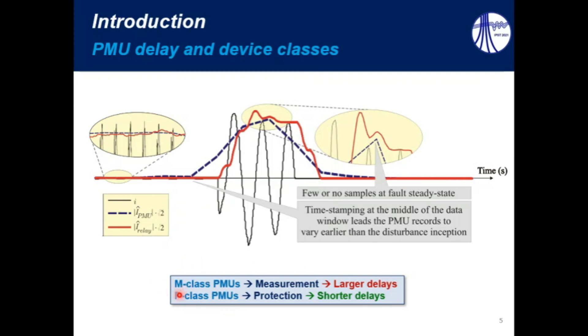And we have also P-class PMUs, which use less filtering, but they will present shorter delays. They are more accurate than protective relays during the phasor estimation process, but they still have delays which are shorter than those verified in M-class PMUs.